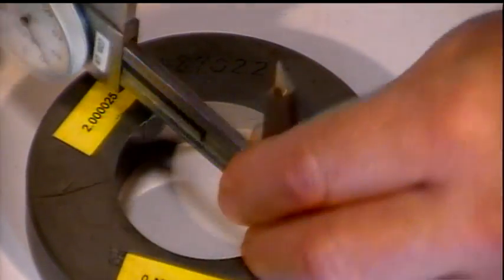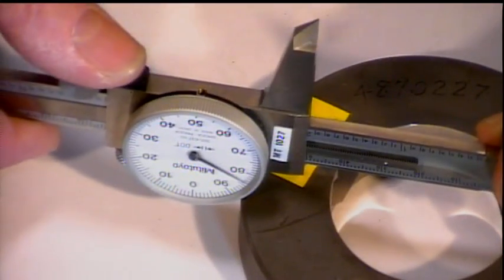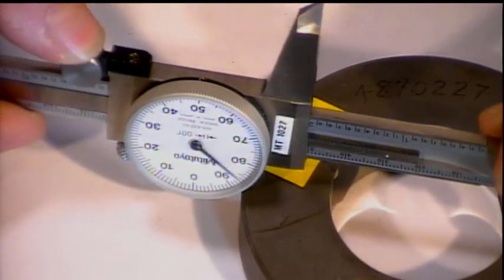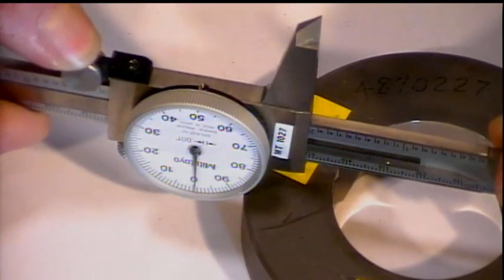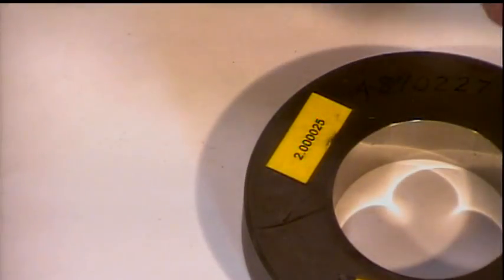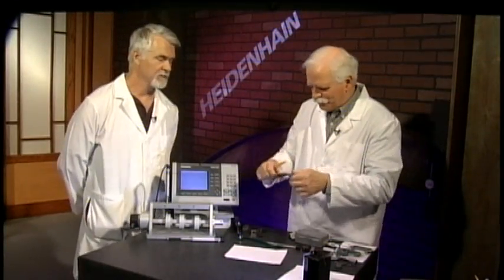The same works for going outward with an inside diameter. Let's try to get this on the camera: as I'm applying pressure outward, if that needle keeps rising and swinging back and forth, that might indicate the gib is a little loose. Those are best left to the calibration lab, but sometimes you have no choice. You can also hold it vertically, and if it drops, the gib is probably too loose. But then again, you want to be able to move it smoothly. So it's a delicate balance between too tight and too loose.